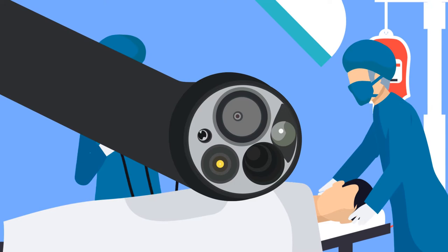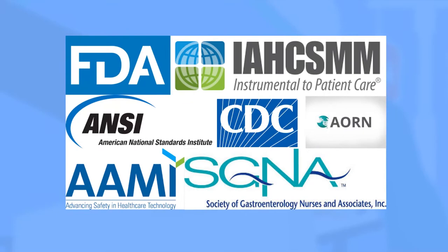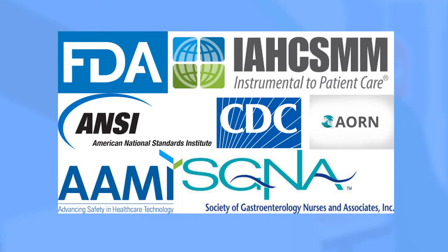Why? You see, endoscopes and other surgical instruments have tiny lumens and channels, and ensuring these tiny lumens and channels are clean can be quite tricky. Patient safety is why multiple agencies have issued guidelines that recommend that hospitals' sterile processing departments use borescopes to inspect these devices visually.